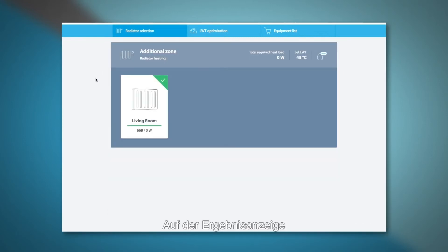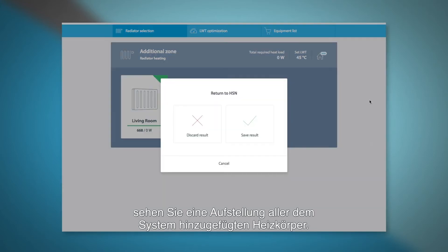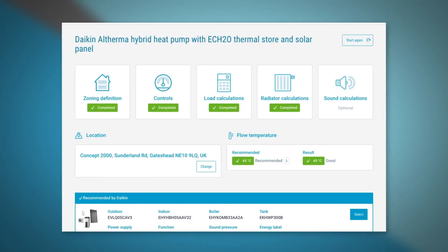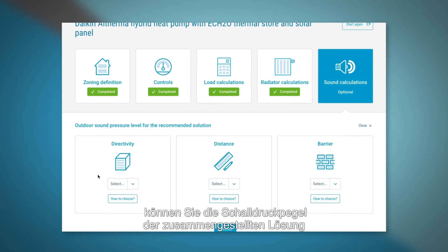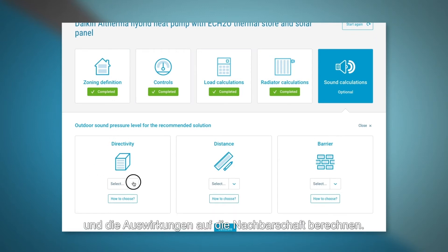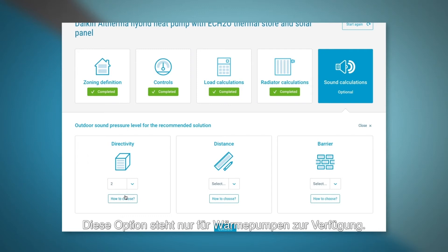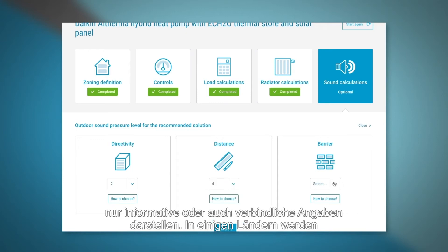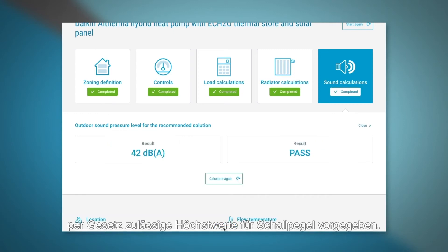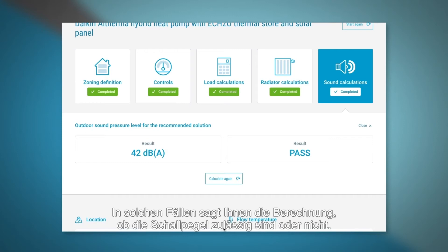On the results screen, you are able to see a kit list generated of radiators that have been added. In the final stage, which is the optional sound calculation, it is possible to calculate the sound pressure level of the selected solution and its effects on surrounding properties. This option can only be completed if a heat pump is selected. The result can be informative or binding depending on the country of installation. In some countries, there is legislation that restricts the maximum allowed sound level of a unit. In such cases, this tool will show whether the system passes or not.